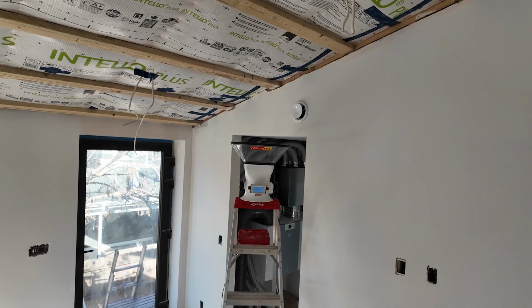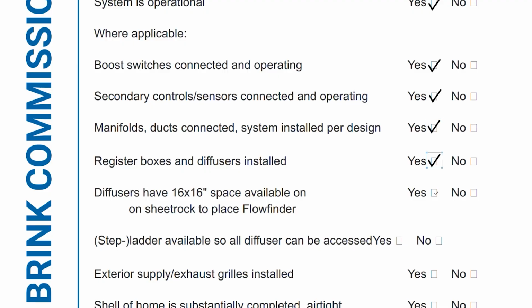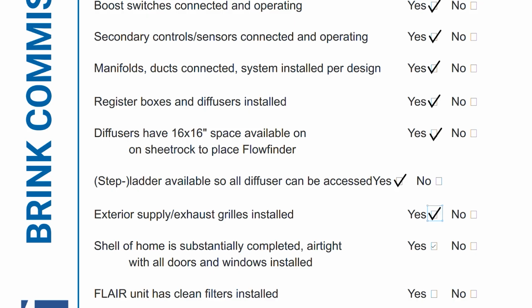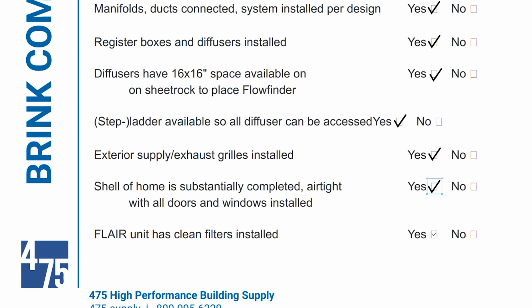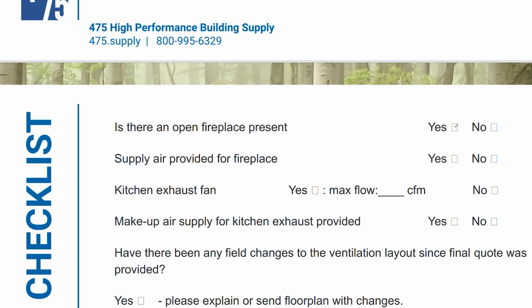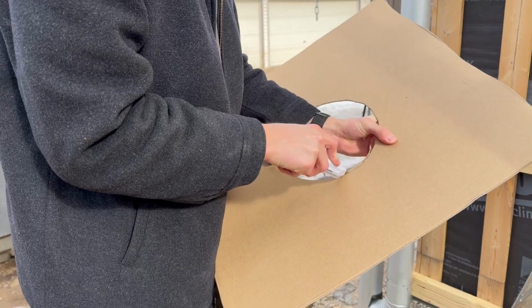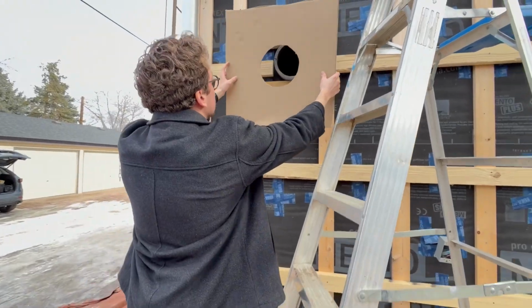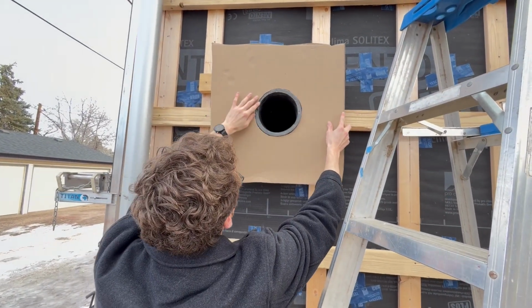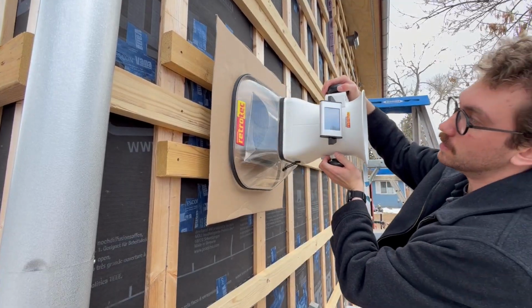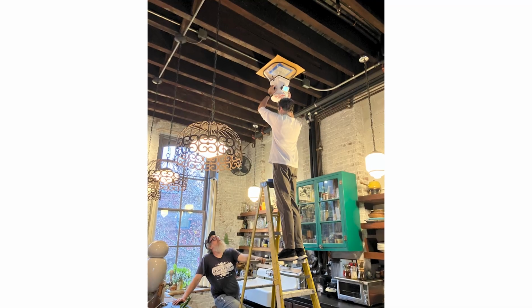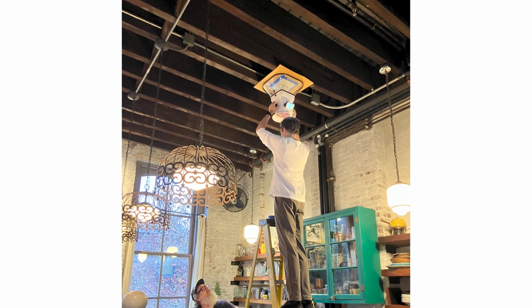They should note if any diffusers are in difficult to reach areas, if the interior finishes prevent a reliable air seal, or if there's less than 12 inches of unobstructed finished wall on all sides of the diffuser. A jig may need to be constructed using cardboard and masking tape to create an air seal in some areas. If the commissioning agent is aware, they can prepare for these conditions.